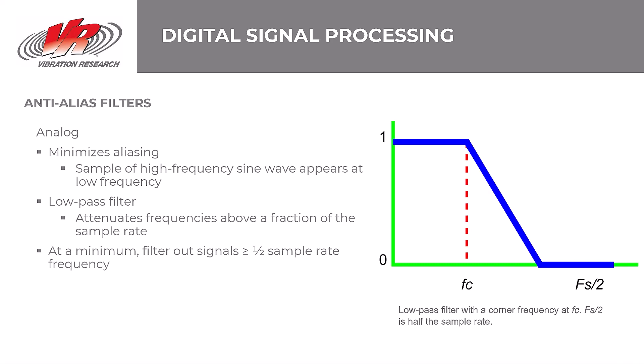Engineers should ensure the attenuation is sufficient for any signal with a frequency greater than or equal to half the sample rate. For instance, if the sample rate is 2,000 hertz, frequencies at or above 1,000 hertz could lead to aliasing. The engineer might struggle to confidently determine if a 1,000 hertz frequency is, for example, 1,500 hertz or 500 hertz. With proper attenuation, they can avoid ambiguity and accurately determine the frequency value.